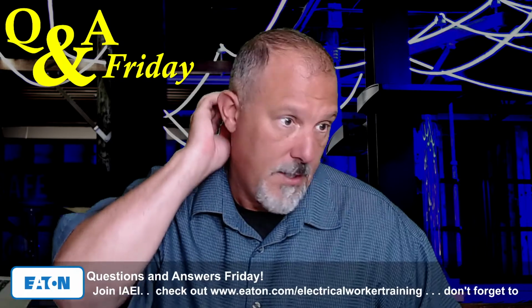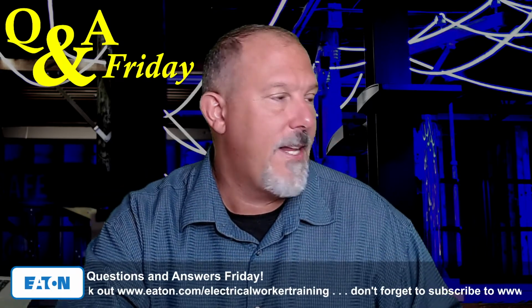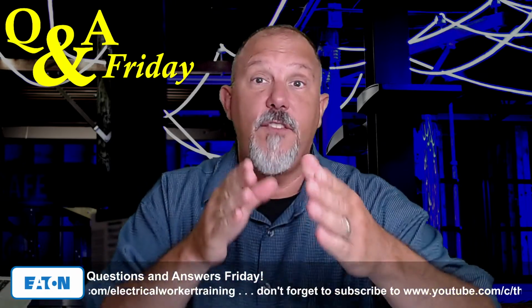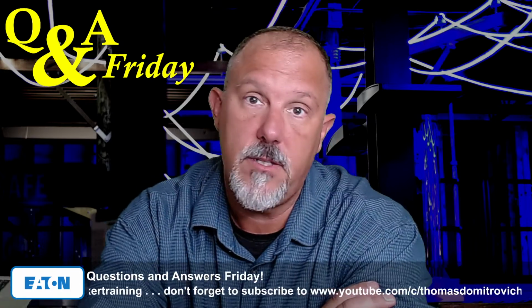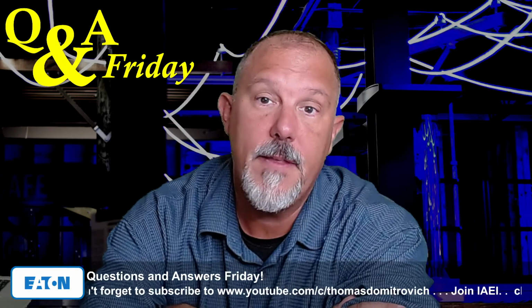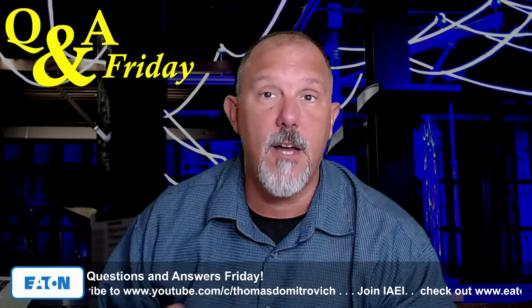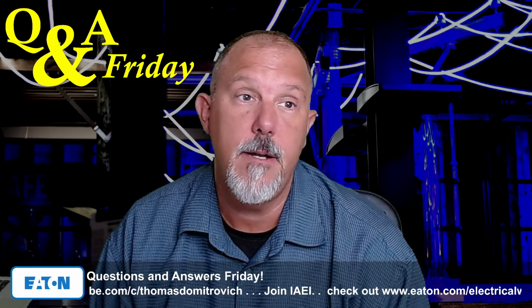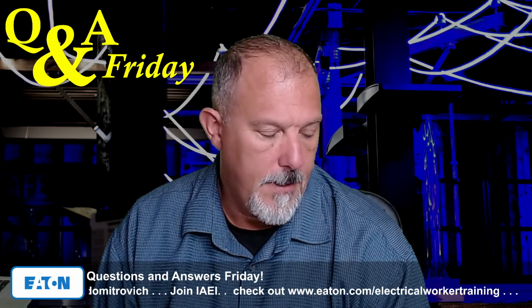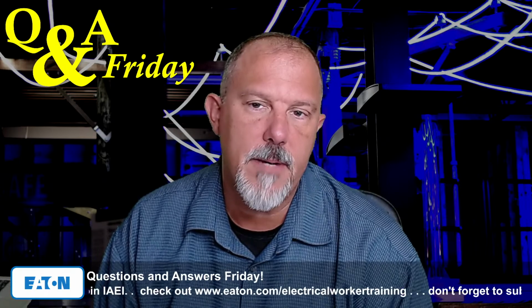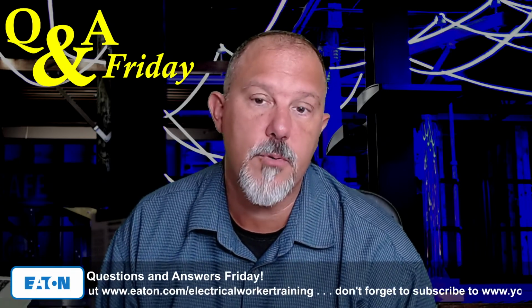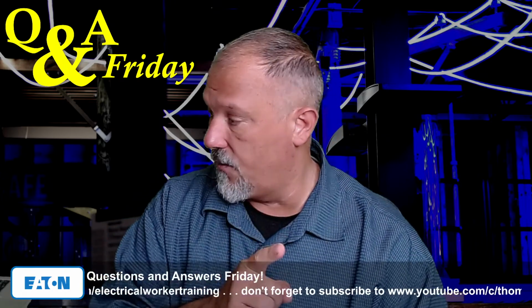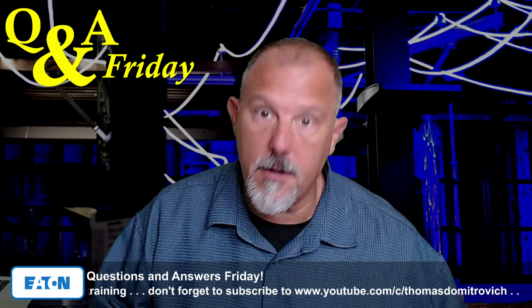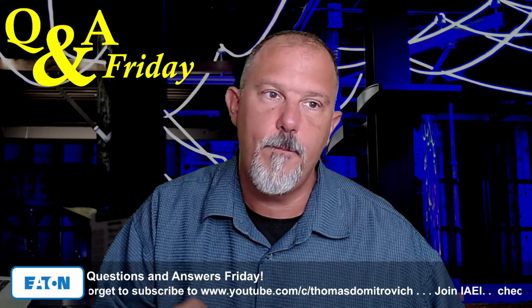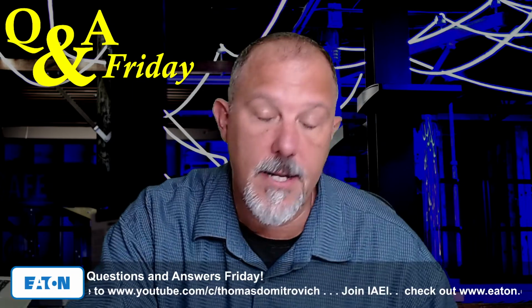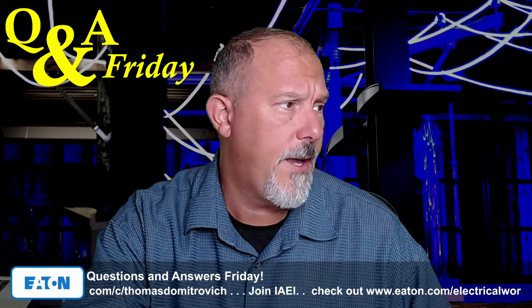Trying some new technologies. Okay, so hopefully, Navneet, that helps you understand. It is about impedance, and if you want to understand how they come up with the percent impedances through the short circuit and open circuit testing that's done on transformers, I don't have a video on that. There's a lot of material in textbooks. I would reference the IEEE color books. I'm not sure which one. What I might do is get my transformer guys and talk about how we determine percent impedance. I'll work with my transformer people and we will get a live session put together on how a manufacturer establishes the percent impedance of a transformer. So stay tuned for that one, Navneet. Hopefully you can tune into that when we do that.